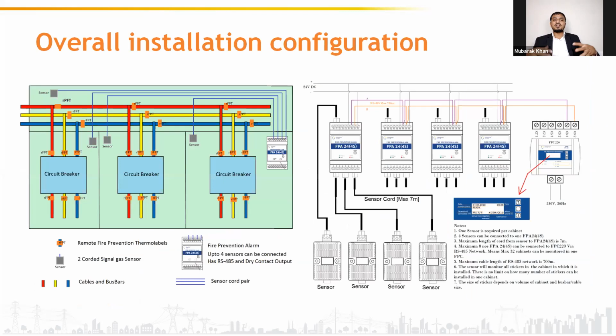Okay, just an electrical layout, how it will look inside the electrical panel. I have taken an example of a circuit breaker panel where we have one incomer, two outgoing, and one busbar cabinet. So we have 3 compartments of 1 meter cube each. Sensors will be installed, one sensor in each compartment. RFPTs will be installed at each joint, and all these 4 sensors will be connected to the FPA. Many such FPAs will be connected together through RS-485 communication, and this RS-485 will be communicated to FPC. This is how the overall electrical configuration will look in the actual scenario.